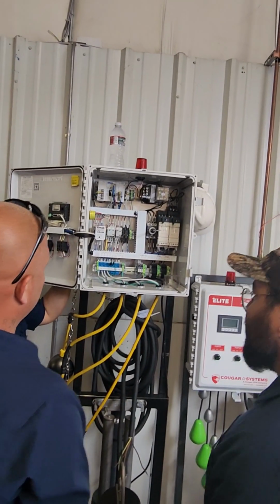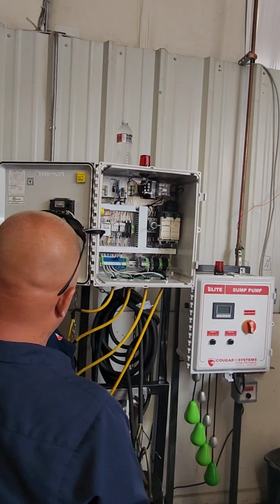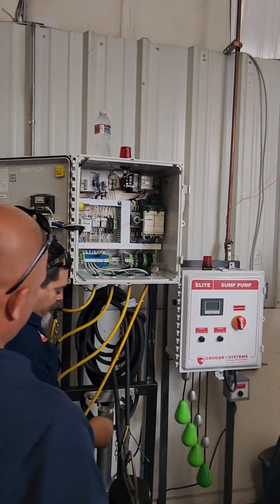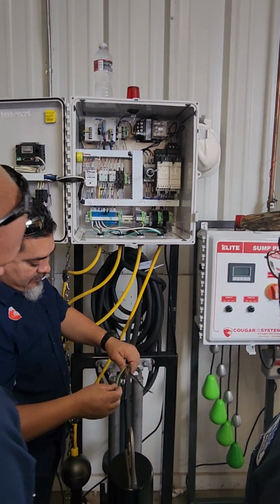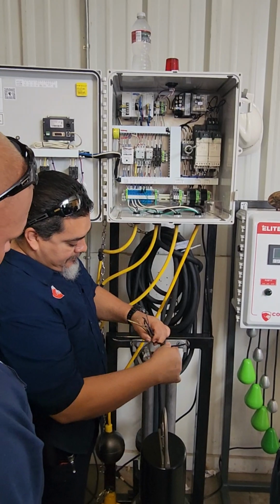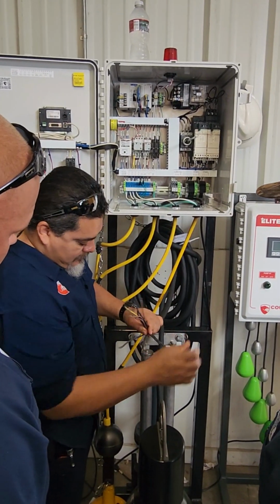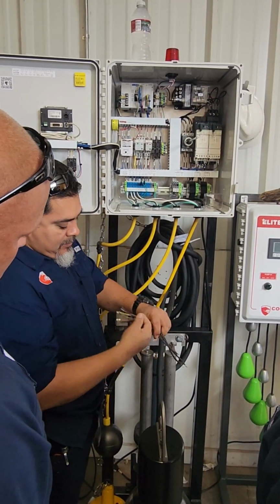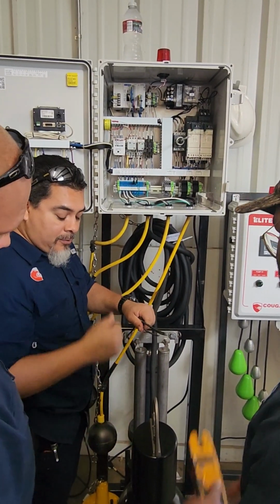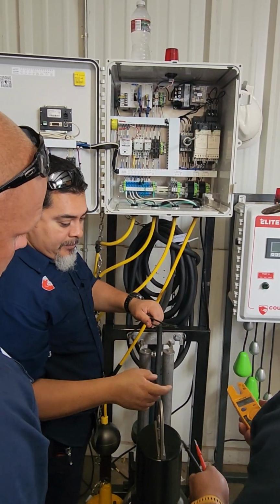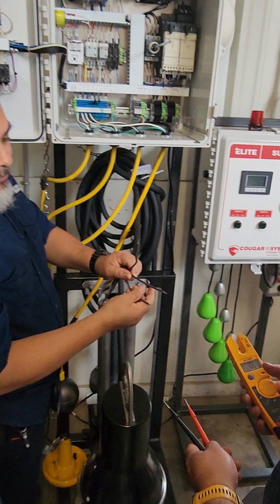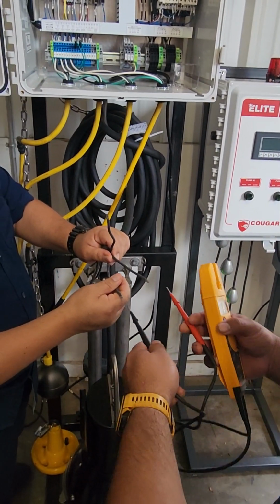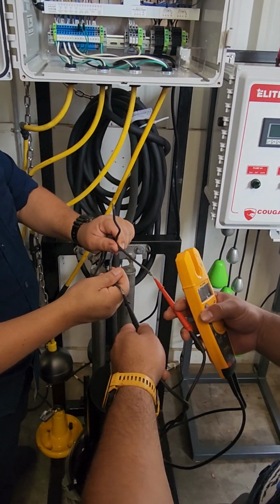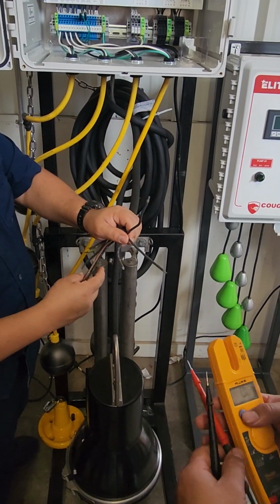Something's going on. Look, if it's a direct short, it's something else. Something's wrong. Now to check your motors, of course, I don't have these set up, but you check ohms on your pump. Okay, and you get 2 leads. Make contact with your leads, so you won't get it because these aren't tied in.